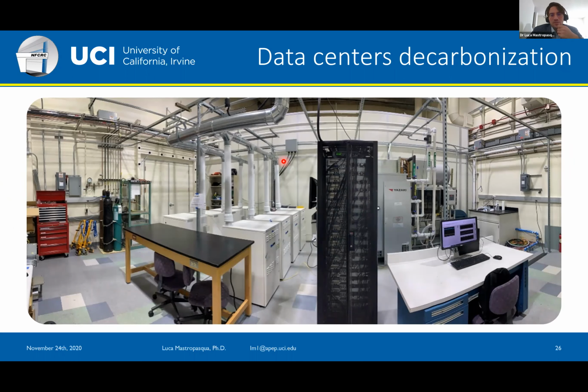The second demonstration we are doing in relation to data centers is for producing both electricity and heat or cooling for the server racks. In this case, we have 8 solid oxide systems placed up here that are directly coupled to the server rack you see in the center of the picture, supplying electricity to it. We also collect all the exhaust lines from these high temperature fuel cells and supply them to an absorption chiller placed behind here to provide cooling loads to the server rack. When we operate these systems with pure hydrogen, we will be able to provide both electricity and cooling to the server rack using renewable energy.